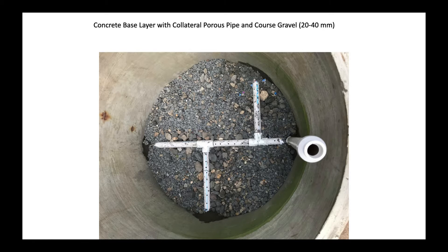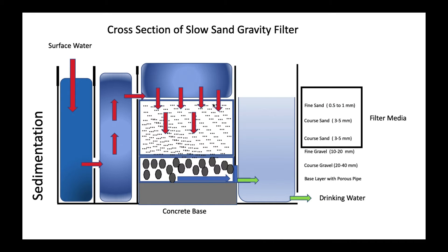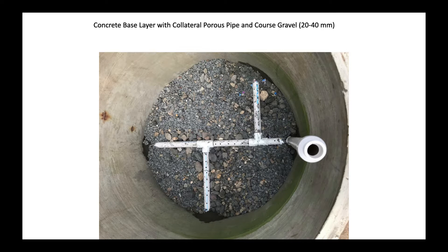This is the base layer with a porous pipe. There is a central pipe connected with laterals to enable water collected from various parts of the slow sand filter to be centralized to a central pipe. Water is filtered throughout the slow sand filter and cannot enter a single pipe, so laterals are made. The large stone particles are called coarse gravels, which prevent blockage of the porous pipe.